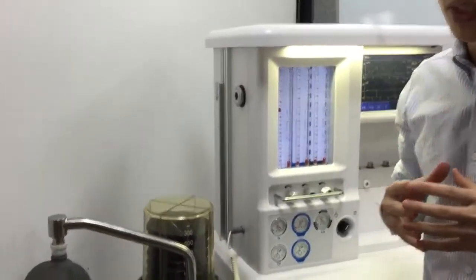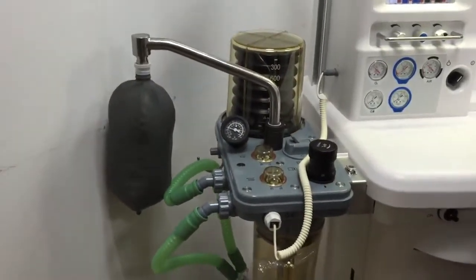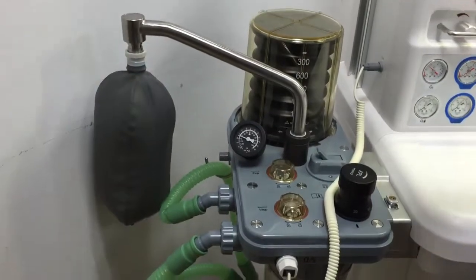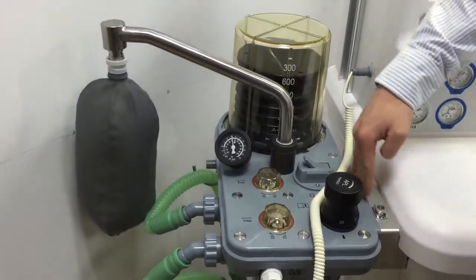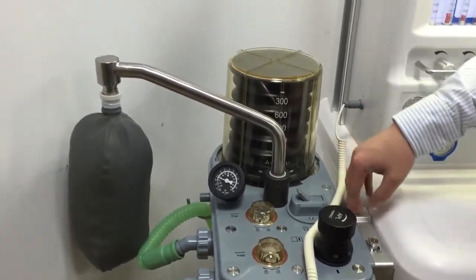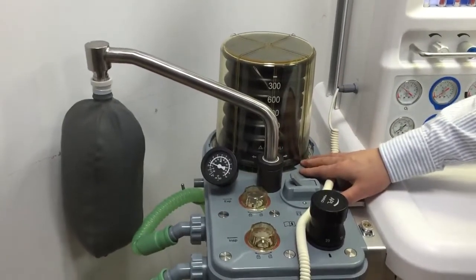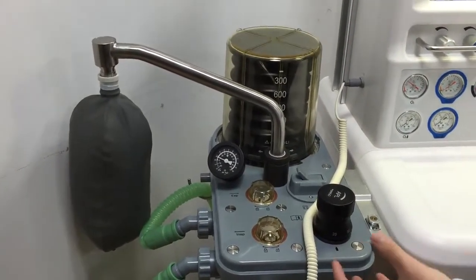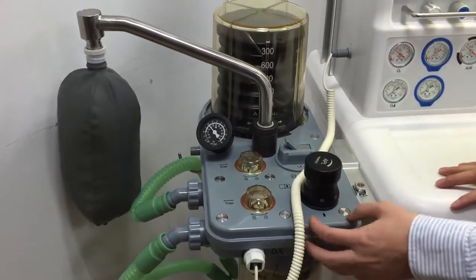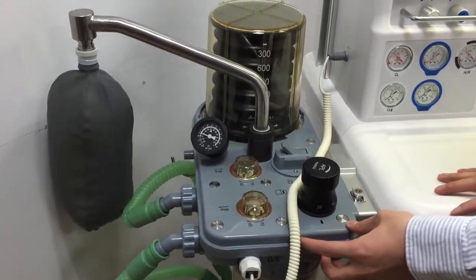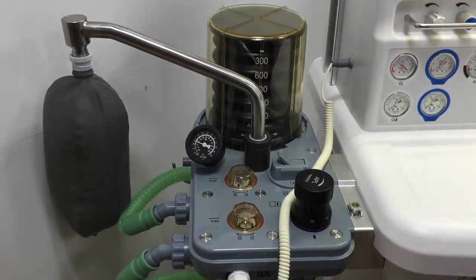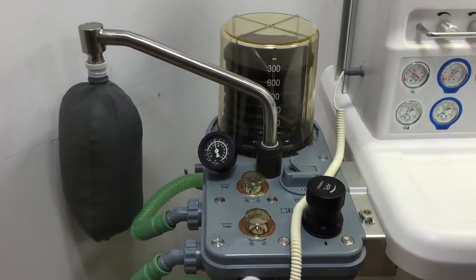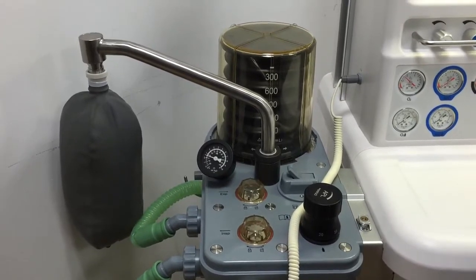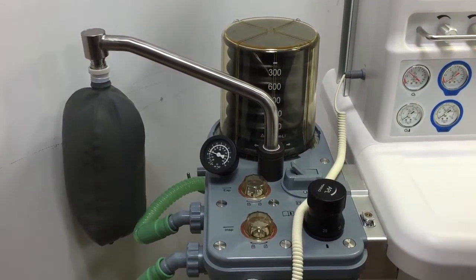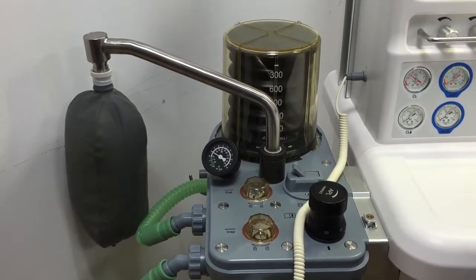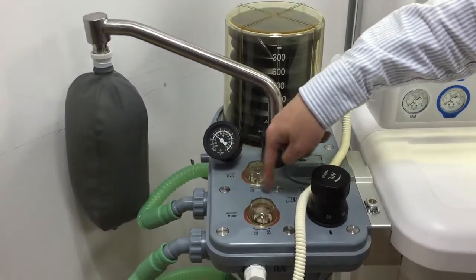Do we have a heater system? Yes, of course, and even better. The universal, or maybe the original or popular, design for the heater system was just to heat the area like here. Some of them use heater wire for the whole body, but usually for the whole body, heater wire needs metal material for the absorber system. But we are using plastic, ABS plastic. If we are using ABS plastic, it easily gets heat, but how to keep it warm? Actually the most important part for the heater to avoid condensation is the inspiratory port and the expiratory port.